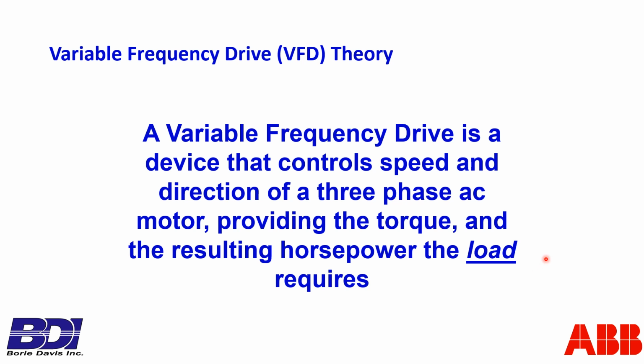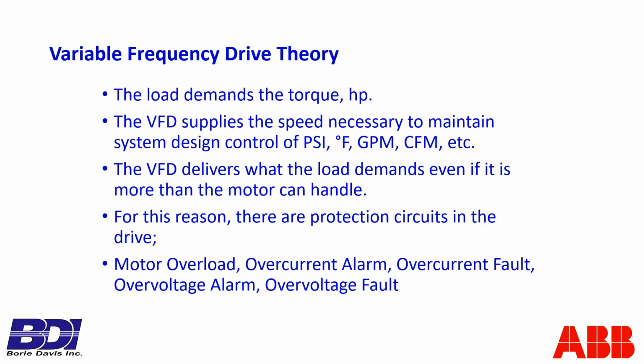A load could go up due to a bearing wearing out, or belts getting out of alignment, adding side loads to the system. So if you're having a problem with motor overload, you need to go look at the load. The load demands the torque and the horsepower. The VFD supplies the speed necessary to maintain the system design control of the pressure, temperature, or GPM, or whatever we're trying to control. The VFD delivers what the load demands, even if it's more than the motor can handle, as I just mentioned. For this reason, we have protective functions.